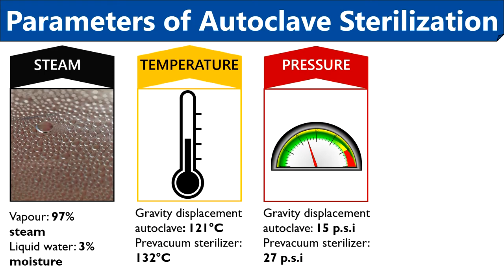Temperature and pressure are the other two parameters of an autoclave. Generally an autoclave uses dry saturated steam under elevated temperature and pressure to ensure potential microbicidal activity. A gravity displacement autoclave is operated under 15 psi pressure and 121 degree Celsius temperature, whereas a pre-vacuum sterilizer is operated under 27 psi pressure and 132 degree Celsius temperature. Here psi is the unit of pressure, i.e. pounds per square inch. If pressure within the vessel is increased above the atmospheric pressure, it will also increase the boiling temperature of water within the pressure vessel, and this increase in boiling temperature will convert water into steam.